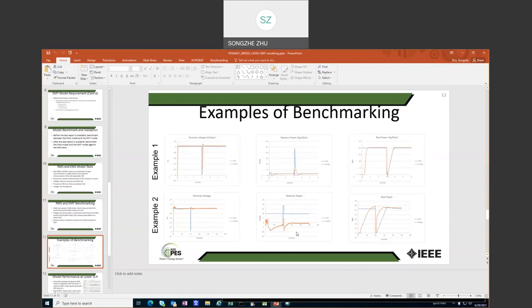So here are some examples of the benchmarking between IMS and the EMT model. The top row is one example, and the bottom one is another example. You can see the voltage is pretty close between the two. And then if you look at the middle one, that's the reactive power. In those examples, they are not too different. In the second one, the initial conditions are not adjusted exactly the same, so it's just a little bit off, but the shape is quite similar. Then the last column is the real power. You can see for the top one, it matches very well. But the second one, they are different.